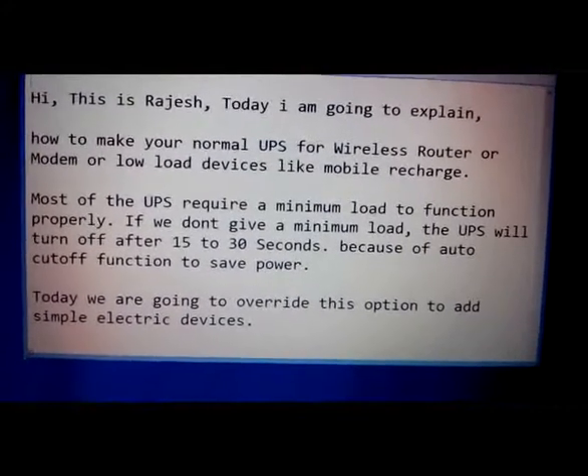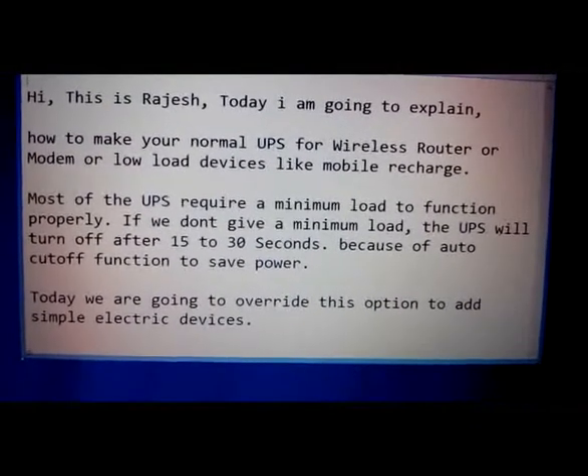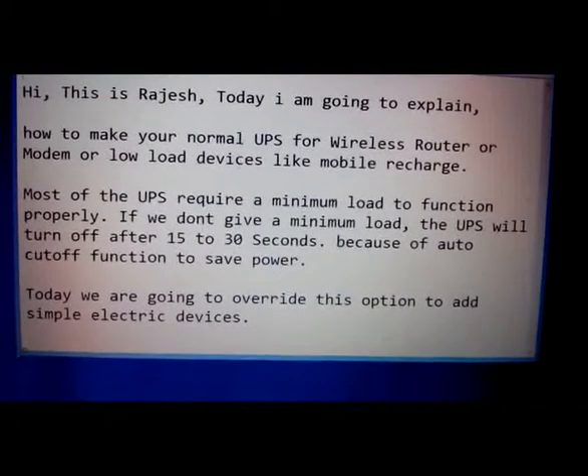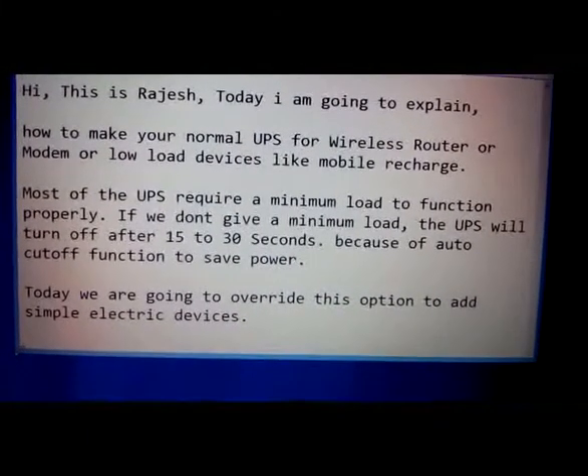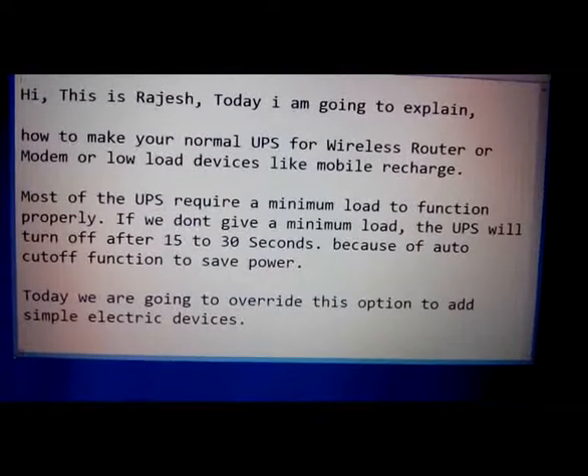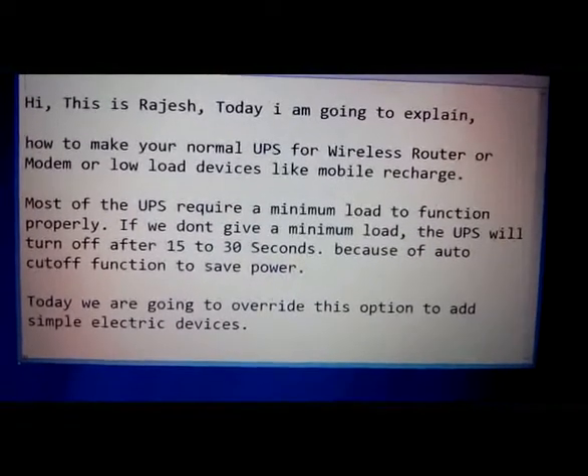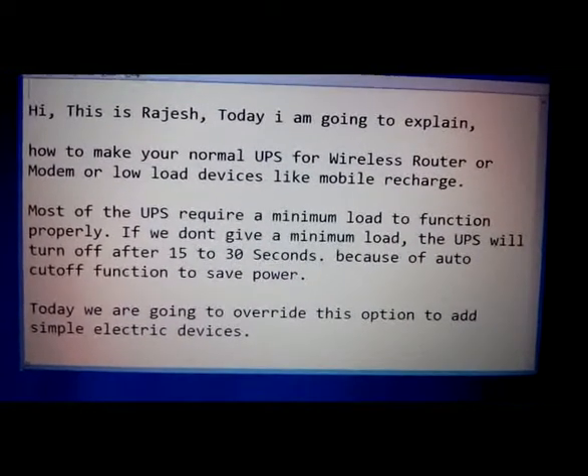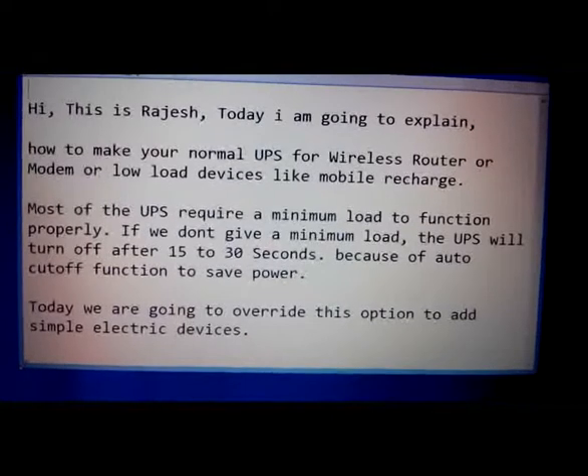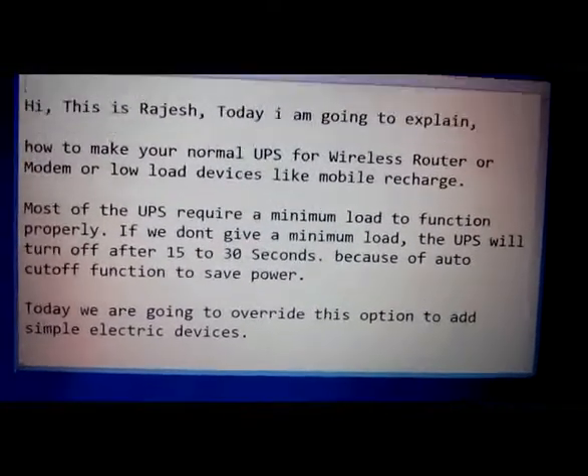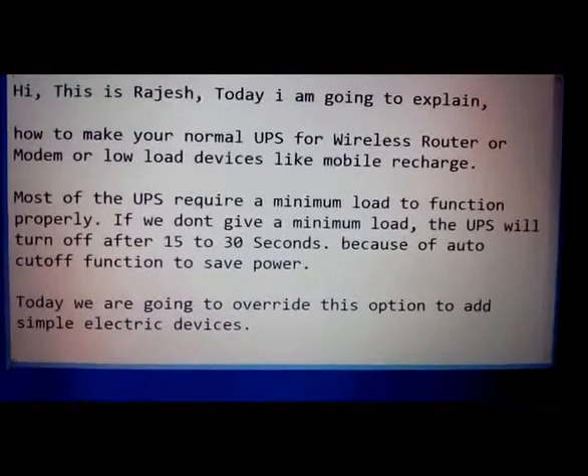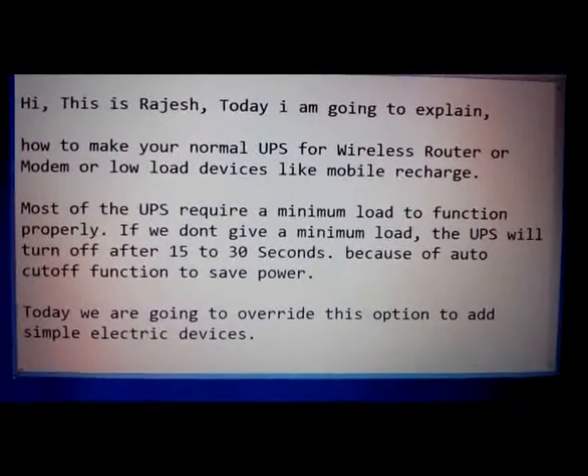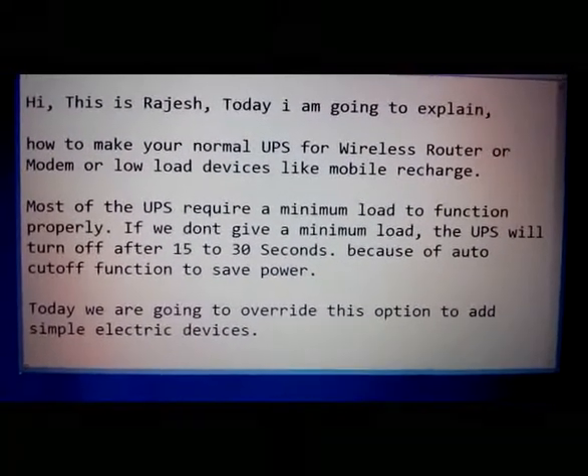Most of the UPS require a minimum load to function properly. If we don't give a minimum load, the UPS will turn off after 15 to 30 seconds because of auto cutoff function to save power. Today we are going to override this option to add simple electric devices.